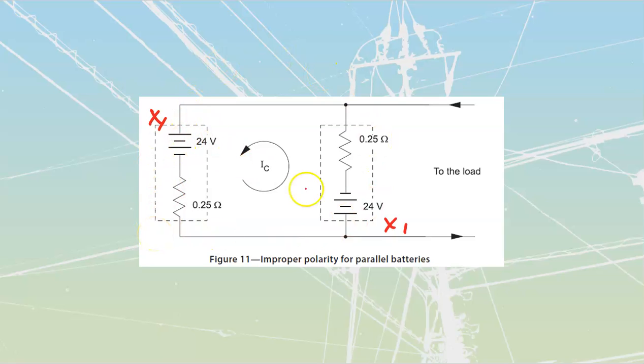It's basically going to be the sum of these two voltages, 24 plus 24, so 48, over top of half an ohm, 0.25 plus 0.25, which means we'll end up with a large amount of current - they calculate out to 96 amps.